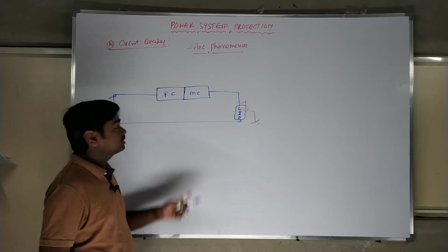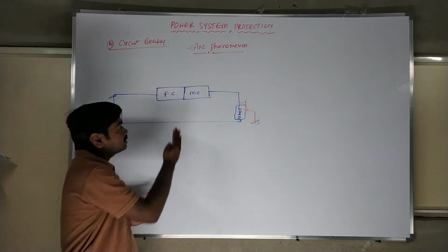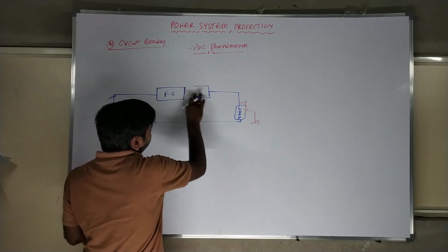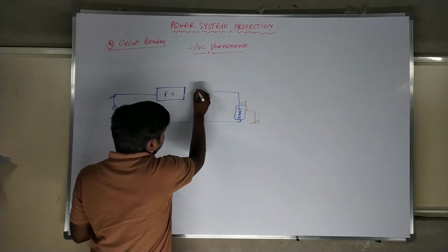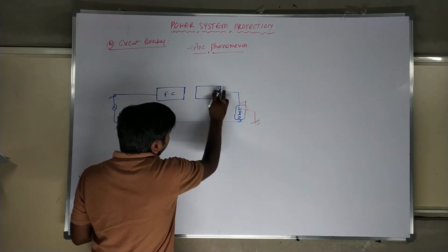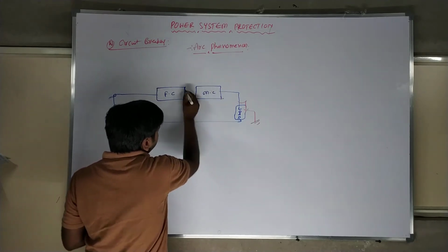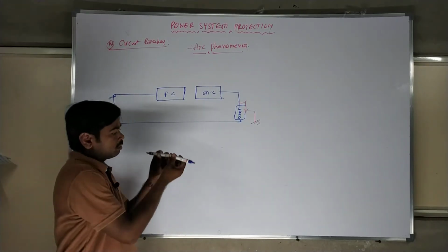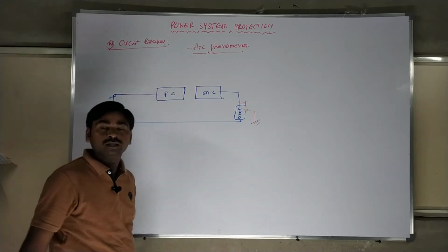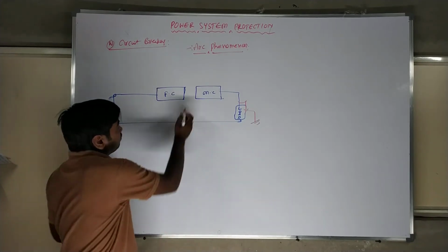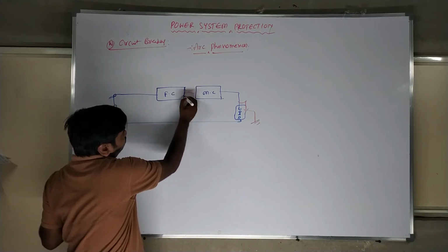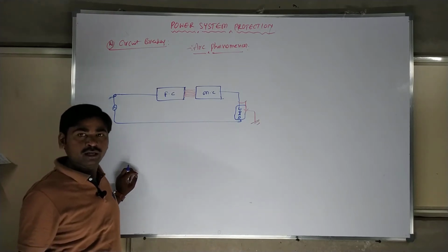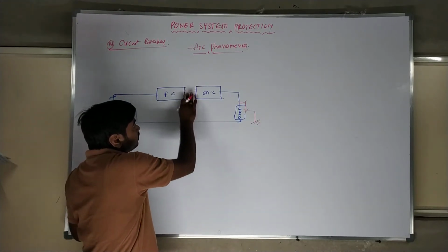Therefore, in the circuit breaker, the moving contact should be separated. The moving contact moves some distance to isolate the circuit. When high voltage and high current are flowing through the contacts and the contacts are separated, an arc will strike in between. The arc takes place because of the high current and voltage, with a gap in between.